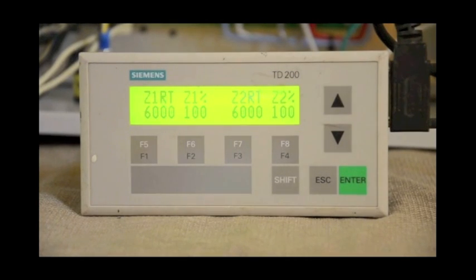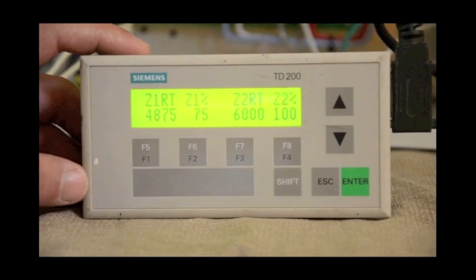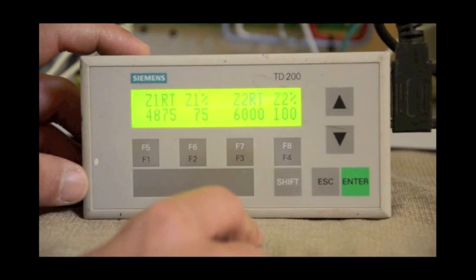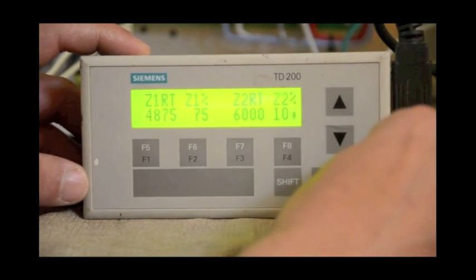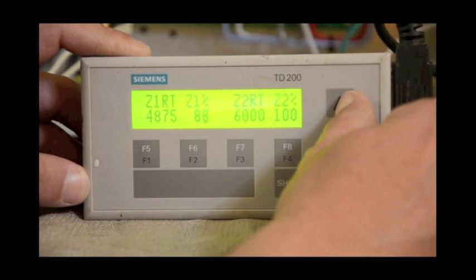Independent zone run times can only be adjusted using the handheld. Going to the F4 screen, press enter until the cursor is flashing under the correct zone and percentage. Using the up and down arrows, you can now independently adjust the percentage of the pump run time dial for each field. In this case, zone 1 is now set to 75%, zone 2 is 100%. I'll go ahead and adjust that back up to 100%.